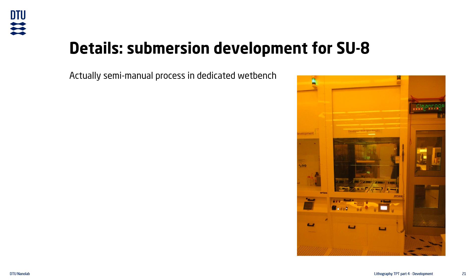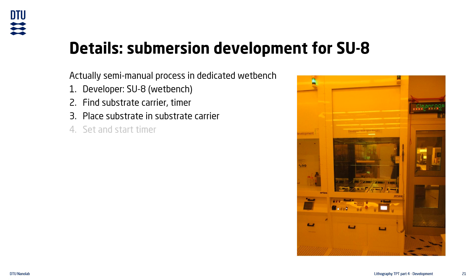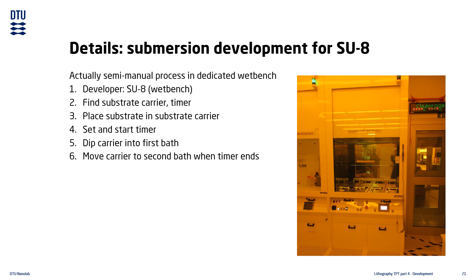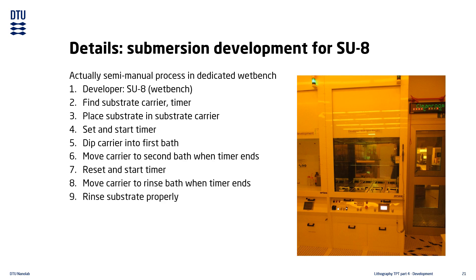For development of SU-8 resists, we have a dedicated wet bench. The process is semi-manual, as users normally do not have to fill chemicals into the submersion baths, but must manually move the wafer carrier from bath to bath. You start by placing your substrates into the wafer carrier, set the timer, and start it as soon as you submerge your carrier into the first solvent bath. When the timer ends, transfer the carrier into the second solvent bath and restart the timer. When the timer ends again, transfer the carrier into the third bath, which is the rinsing bath. After rinsing properly, transfer the carrier to the drying station, leave the carrier and wafers to dry, and clean the wet bench.